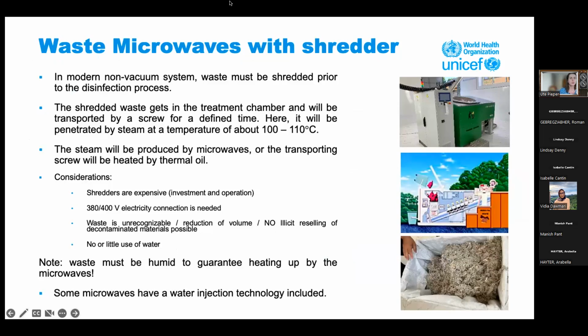The next and last one I would like to introduce is the waste microwave with shredder. Microwaves use microwaves to heat up the waste, so it does not use external steam connection or steam production. It uses microwaves to heat up the humid condition of the waste. The newer microwave systems even have water connections where they add water to the waste in case it's too dry, so the microwaves can heat the waste up to 110 degrees. Then it's stored for another half an hour at these temperatures to ensure full decontamination. These systems use three line electricity connections, 380 or 400 volt.